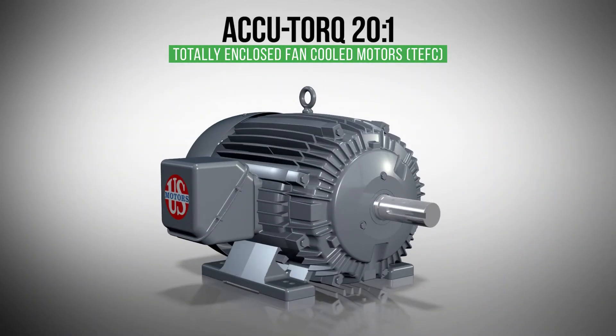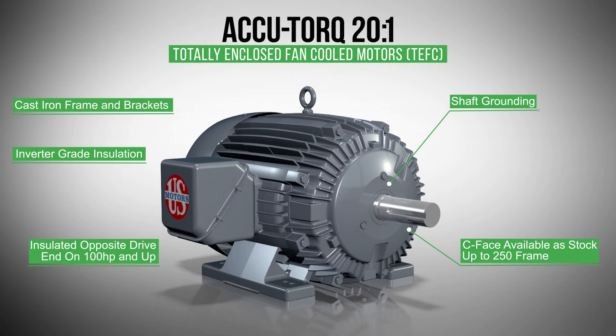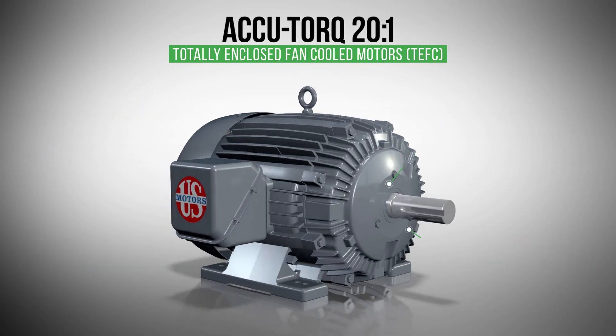Nidec's totally enclosed fan-cooled Accu-Torq motors have many of the same features as our totally enclosed non-ventilated motors, but with some additional features. All ratings come standard with shaft grounding. Motors 100 horsepower and up include an insulated opposite drive end bearing to extend bearing life.